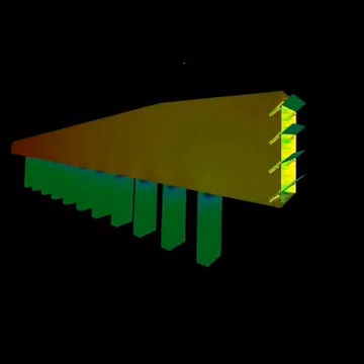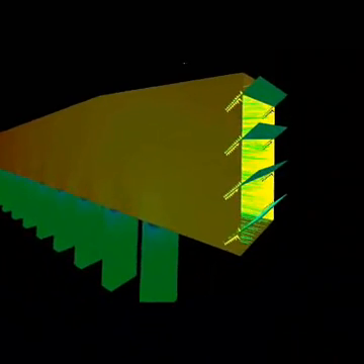This is an air distributor that is part of a hydrogen reformer furnace. Air comes in from the inlet opening. It is then distributed into 11 outlets to supply air to the burners for combustion. As we fly through the channel, the coloring indicates that air velocity is increasing the further we go.